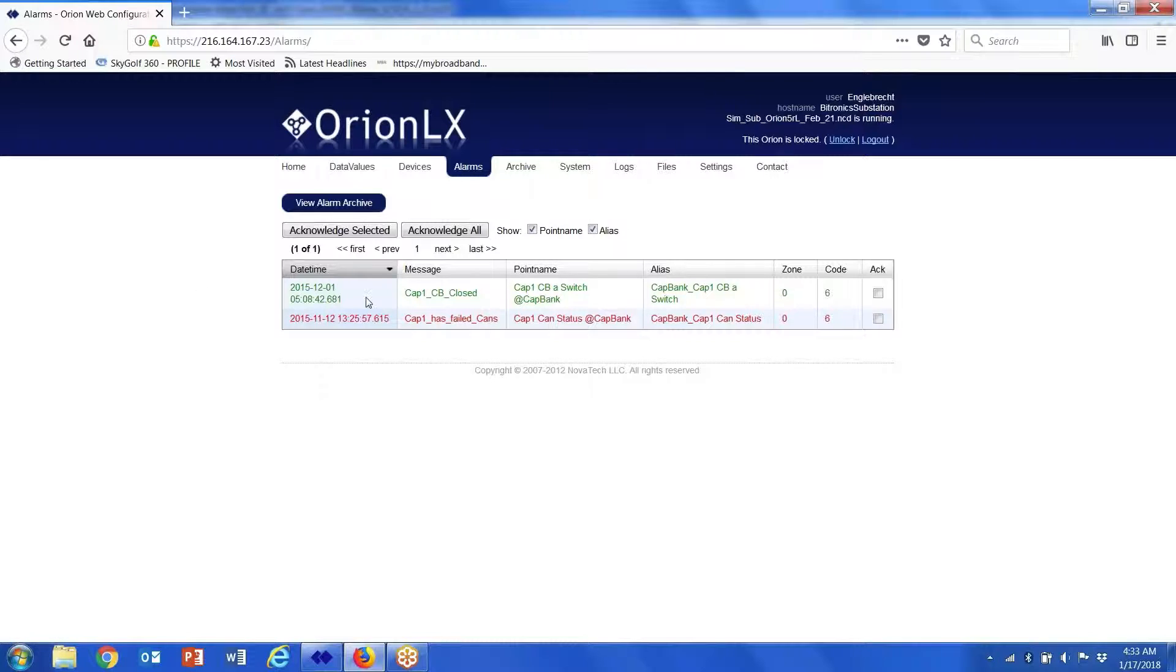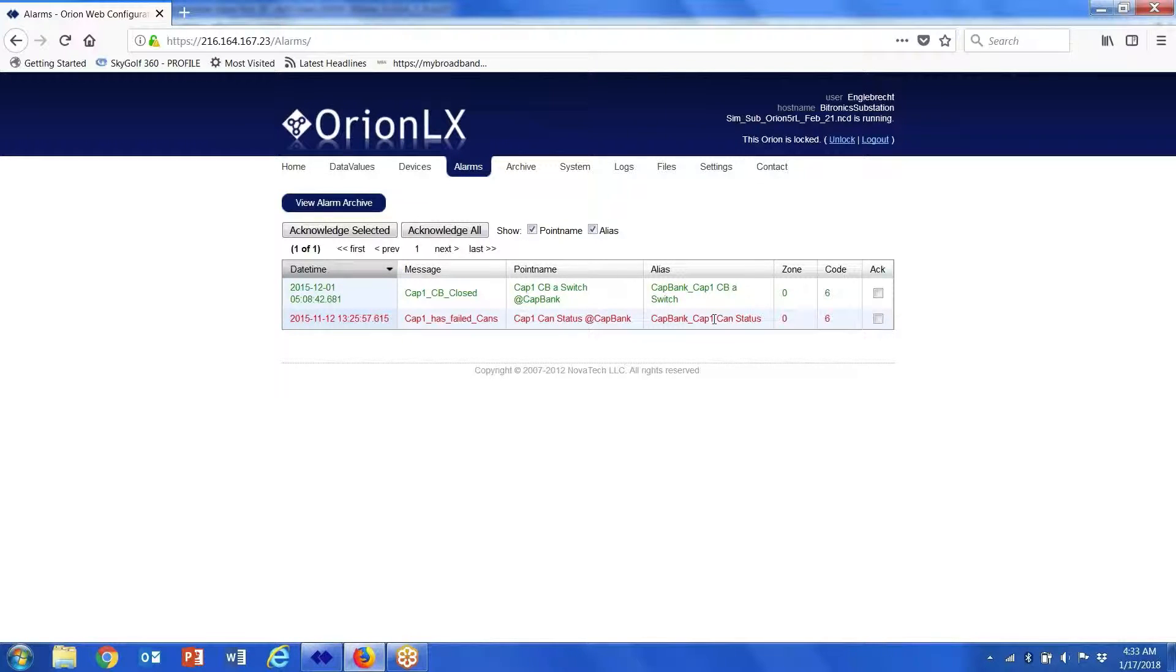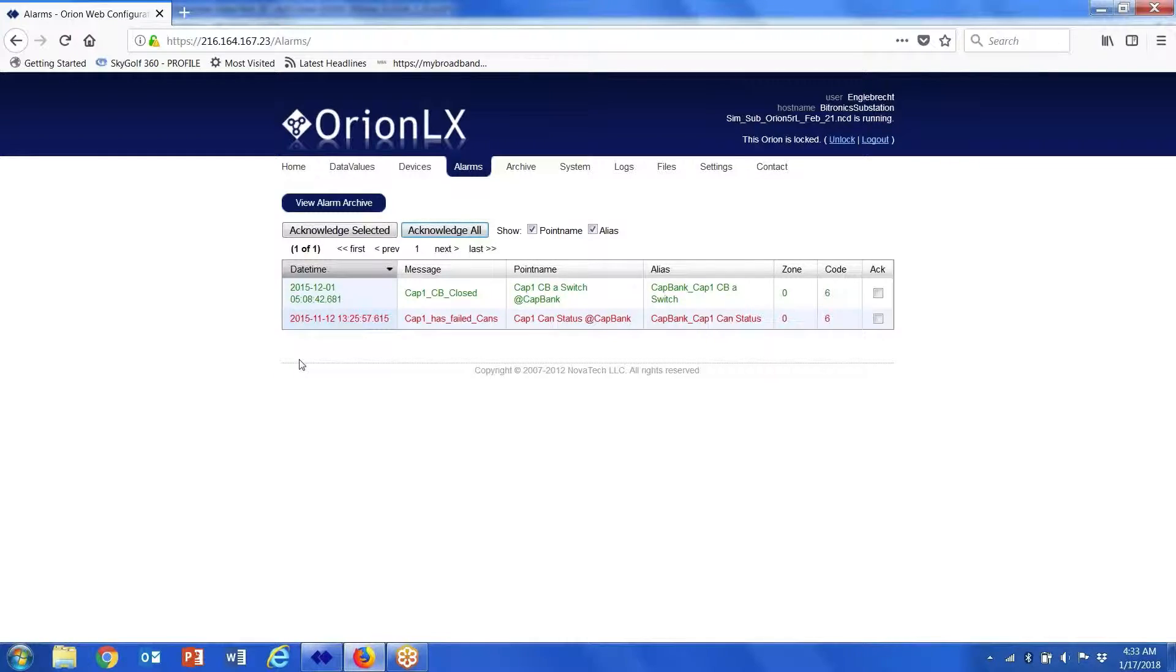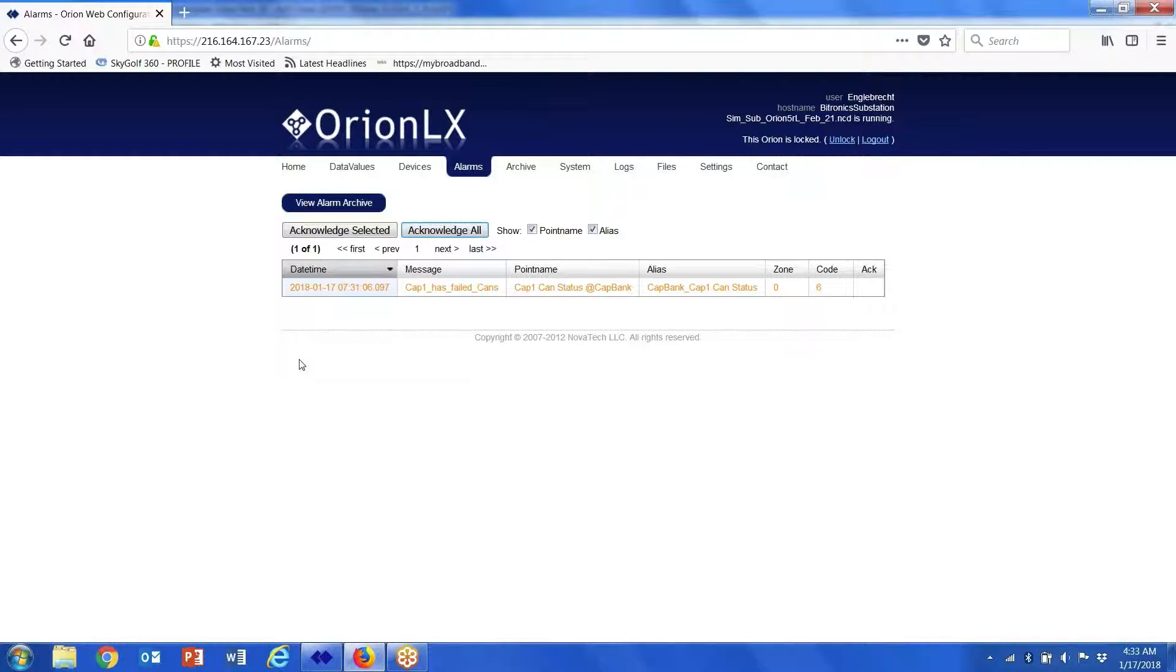These are going to be points that are in alarm and points that have been acknowledged. So if I acknowledge it all, it will change colors. The point that was green went away because it had already been acknowledged—it's no longer an alarm. This particular point has been acknowledged but is still in alarm.